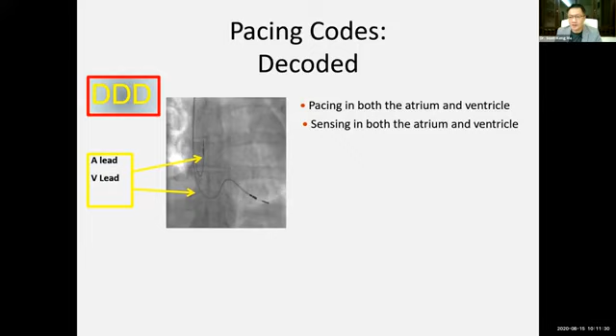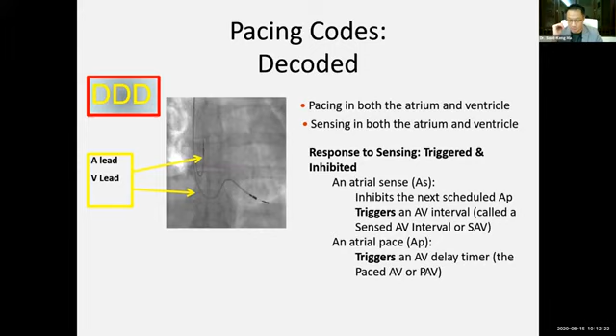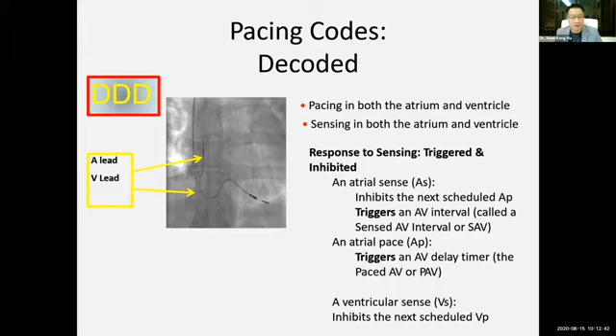If you have the intrinsic atrial sense activity, atrial sense means that you detected intrinsic activity in the atrium, you need to trigger the pacemaker because you need to initiate another internal clock timing cycle called the AV interval. So the clock will tick until it times out and it will look for cardiac electrical activity or initiate another clock. In the same vein, if the event at the atrial level is a pace, atrial pace, it will trigger another clock called the AV delay timer or the so-called pace AV. How about at the ventricular level? At the ventricular level, if you detect an intrinsic cardiac electrical activity, you inhibit yourself. That's why it's dual, both triggered and inhibited at the same time. That's why the letter D in the third position.